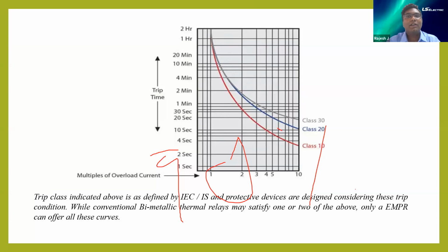All these days we are using our traditional overload relay, the bimetallic overload relay. So what is an overload relay? It's an electromechanical device, a combination of two different metals. That's why we call it a bimetal relay. When current increases, the bimetal property tends to change, a high coefficient material and a low coefficient material. This variation in the coefficient will make the bimetal strip bend, and that will trip the mechanism. So this is the traditional overload relay.